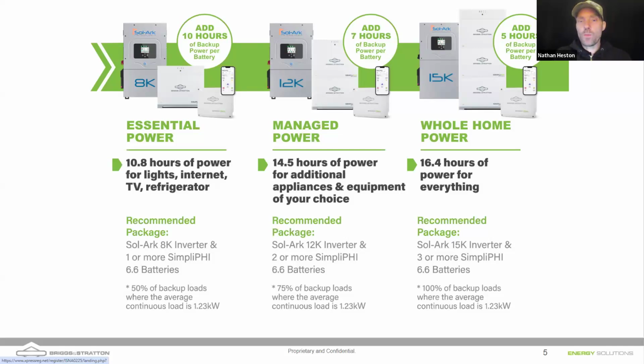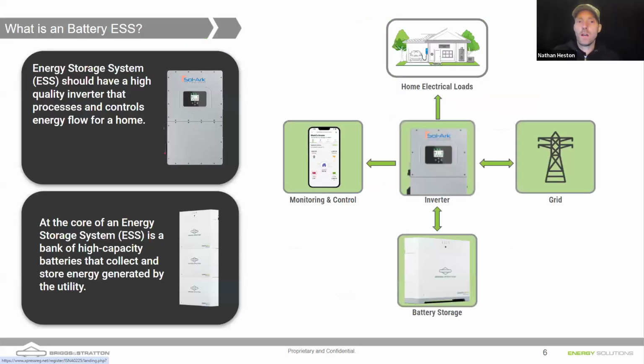Of course, you can always add more backup time by just paralleling more batteries. You can have a very large battery bank to run with your inverter. There's no problem with paralleling more batteries, having a larger bank. Of course, you get more backup time. One of the things I like about working with Sol-Arks and Briggs and Stratton batteries is that you are scaling the power and the capacity independently of each other, right? So you could have a very large bank, get a lot of backup time, but not have to pay for extra power that the inverter could generate that you don't use.